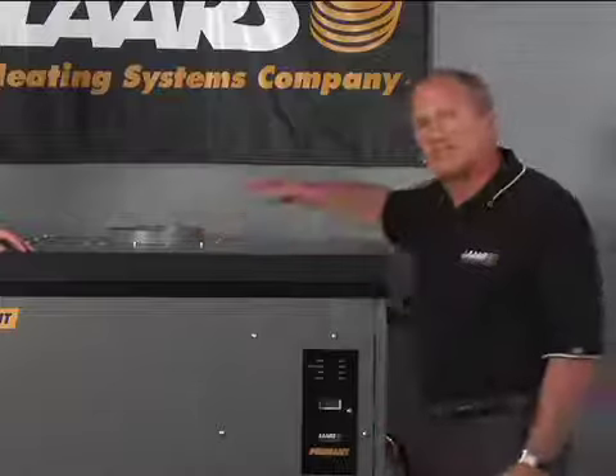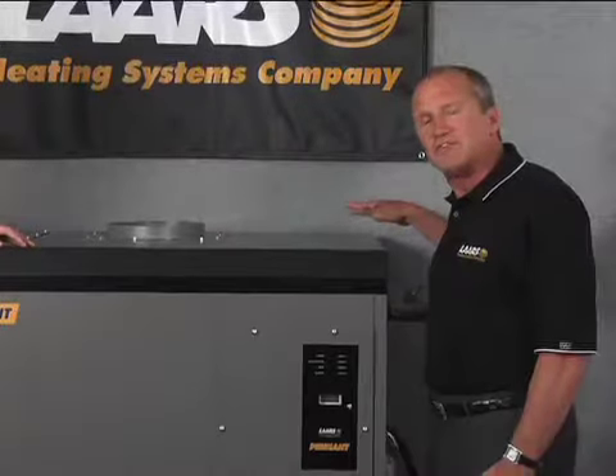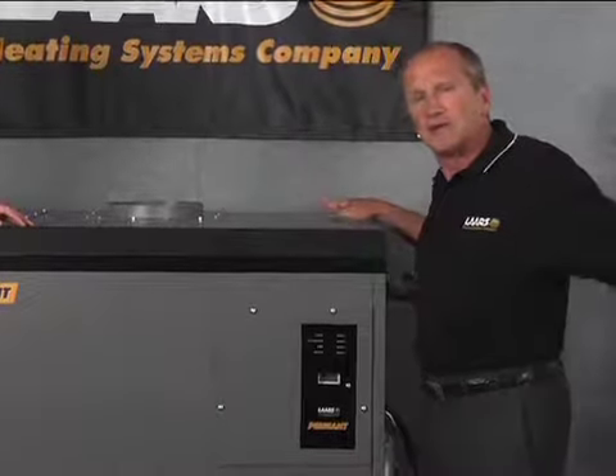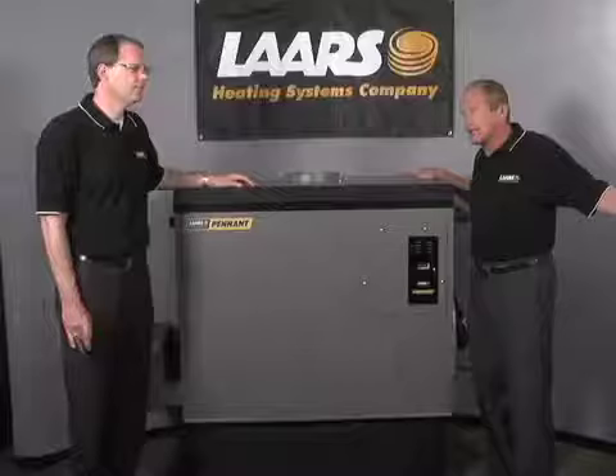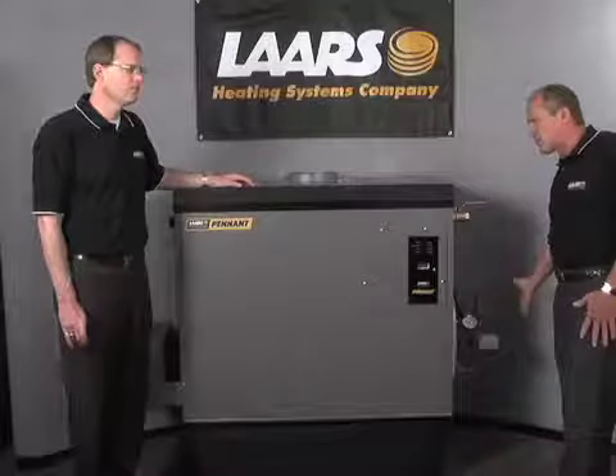When you vent through a chimney, you have to use Category 1 material, which is a Type B vent. If you duct through the side or vent through the side wall, what you have to use is a stainless steel vent, which you can run up to 50 feet through the side wall, and you terminate it on the outside wall. The connections on here are on this side. Tom will speak to that.